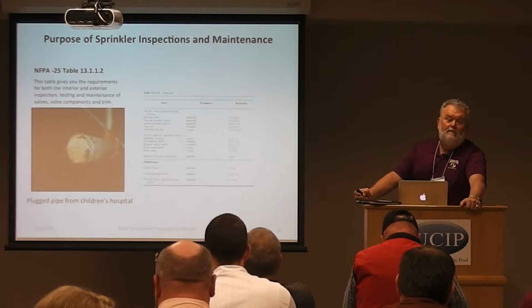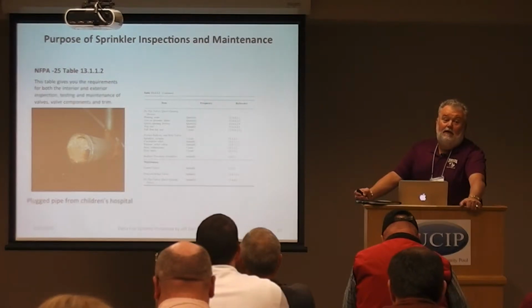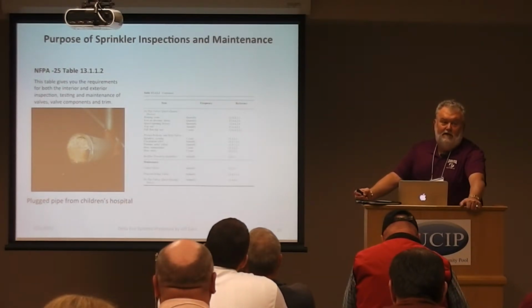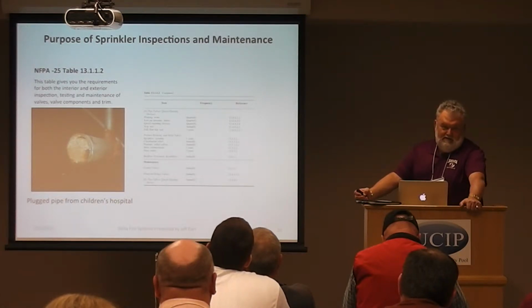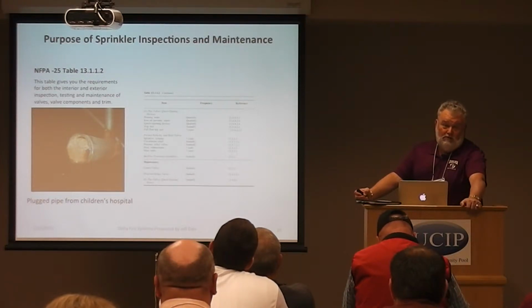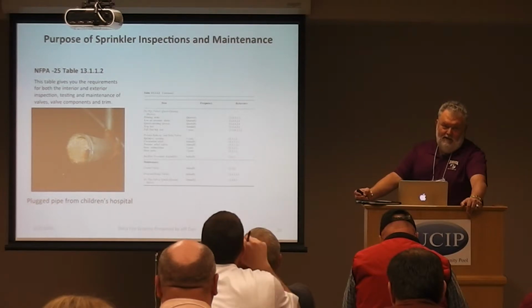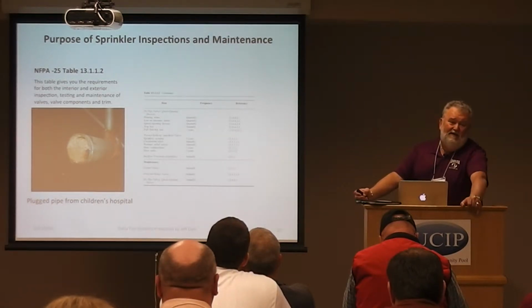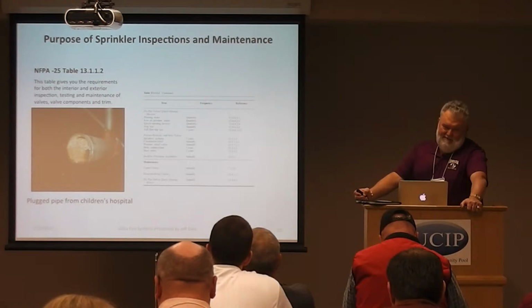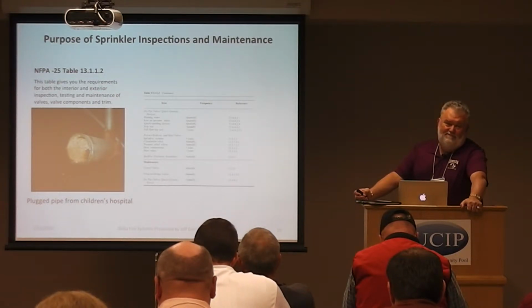Yes, sir. Is that rust that's in there, or is that other debris? That's a combination of that. It could be rust. They have what they call MIC that's out right now. It's a microbe that's actually attacking the internal walls of the piping, and you may get pinhole leaks. If you're starting to get pinhole leaks in systems, it's probably a MIC issue. That picture there shows the pipe looks good on the outside. Right. That's what I'm saying, until you break it, you're not going to see that.